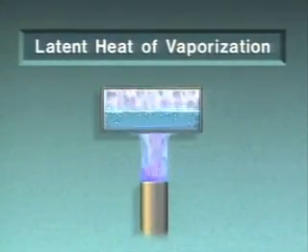The heat that's required to completely change a liquid to a vapor at a certain temperature and pressure is referred to as the latent heat of vaporization. The heat that must be removed or rejected to completely change a vapor to a liquid at a certain temperature and pressure is referred to as the latent heat of condensation. When the refrigerant in a refrigeration system receives heat from the substance being cooled, it receives the latent heat of vaporization and becomes a vapor. When the refrigerant rejects heat, it gives up the latent heat of condensation and becomes a liquid.